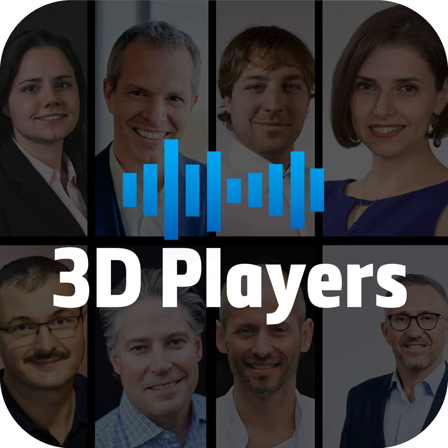But the key question is, how do we do the verification and validation? Verification means, how do you solve the equation properly? Validation is, how do you make sure that your model represents the reality? So with ASME, we've been working for the last 10 years in order to create the ASME V&V 40, which is verification and validation. 40 is for medical device. This element will define in every single step how can we make sure that we are verifying the solver that we are creating, and how do we validate the model? What will be the risk associated with this model?